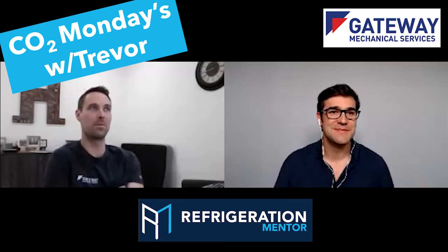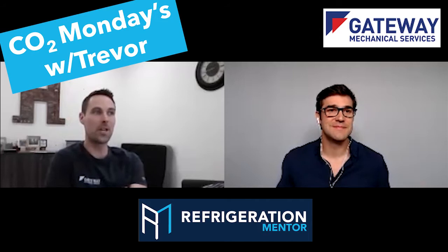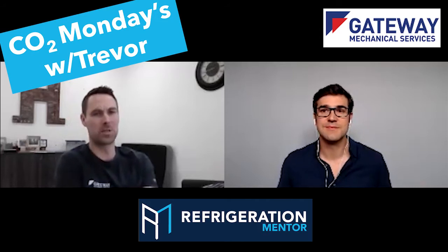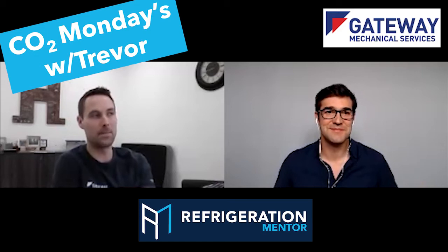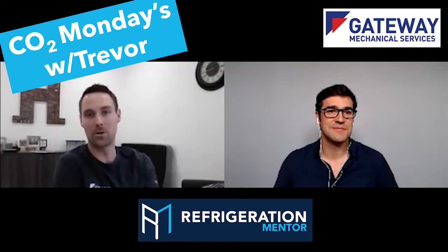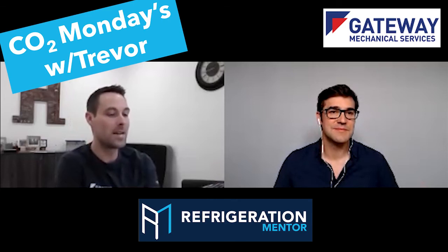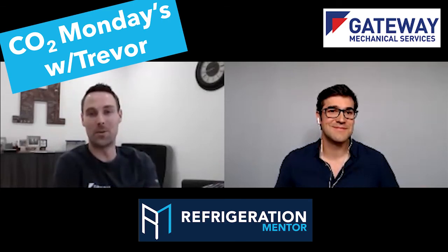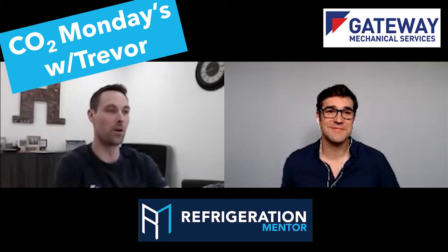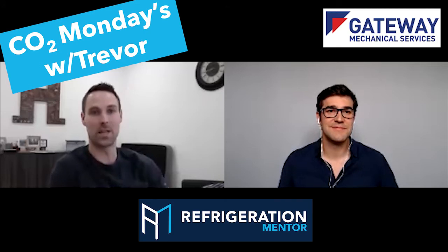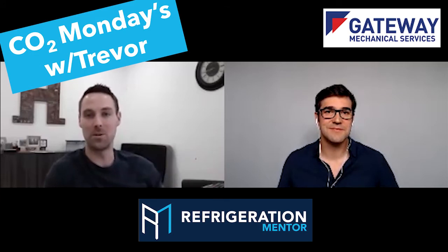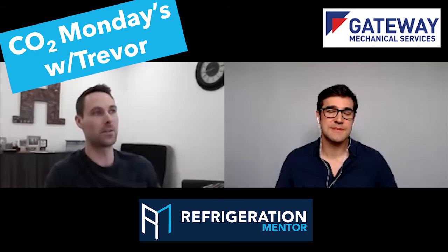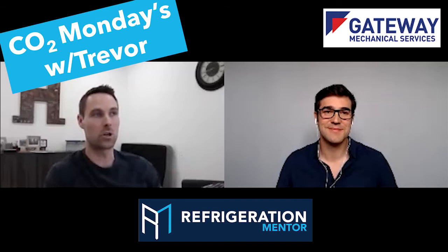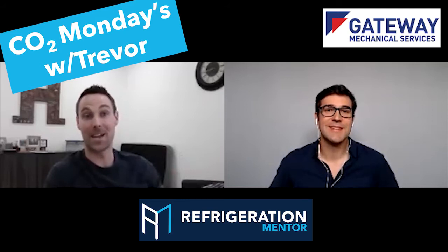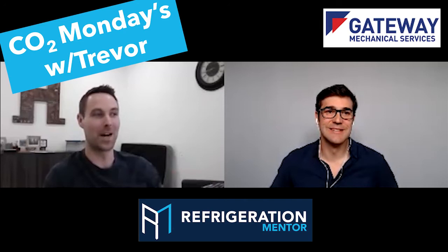Yeah, I would definitely say not fully understanding the new design and really respecting the pressures, and obviously respecting your triple point, creating dry ice. So when you first go up to it, it's definitely intimidating. If you've worked on a lot of HFC stores, then the electrical side of it doesn't really intimidate you too much, like the panel size or anything like that. But definitely the refrigerant part of it at first, the safety and handling, charging the system properly. That is definitely a little bit intimidating, and I'm still working with the guys on that.